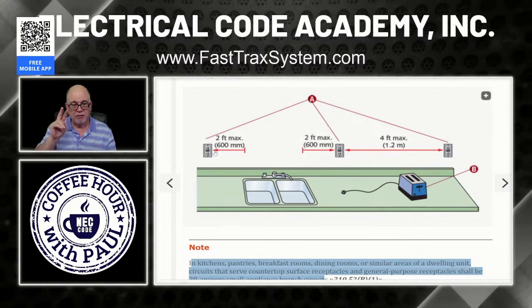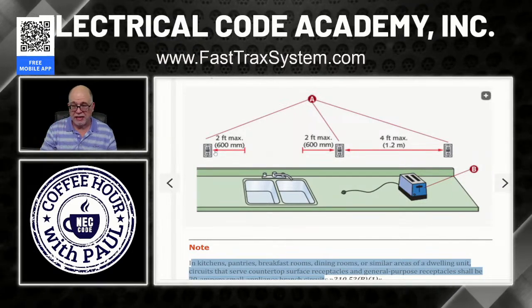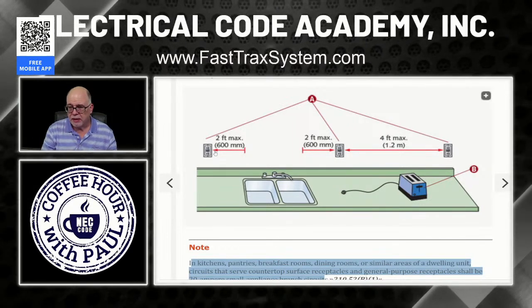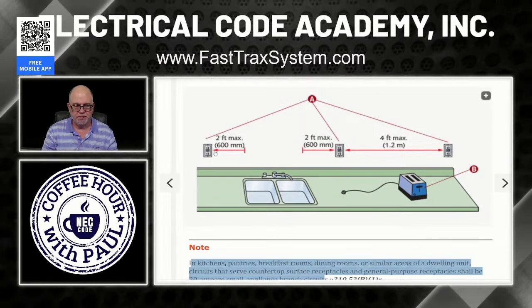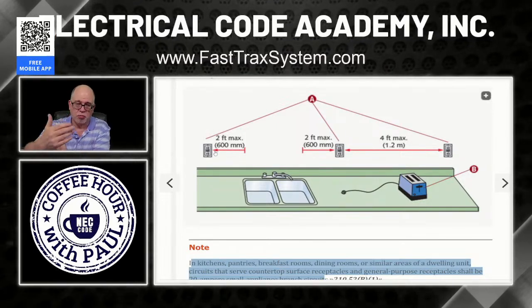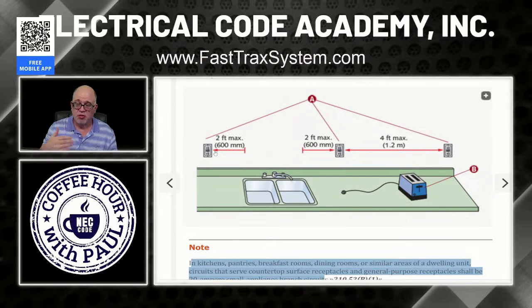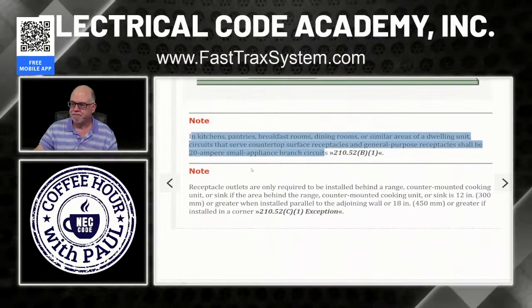Okay, so if you have a minimum of 2 small appliance branch circuits per code, can you have more than 2? Absolutely. You can have 3, 4, 5, whatever you want. But those small appliance branch circuits are going to serve not only the countertop receptacles, but also the wall receptacles all around your kitchen, okay? And your pantry and your dining room, all of those are served by those small appliance branch circuits. Now, I could have 2 for the kitchen and a 3rd one doing the dining room. And all that would be fine. I can have more than 2, but I have to have at least 2, okay?